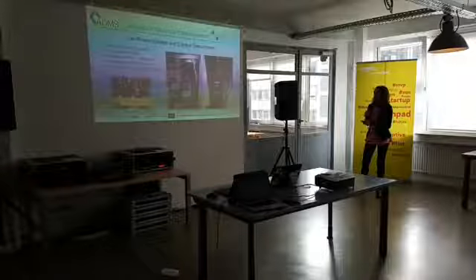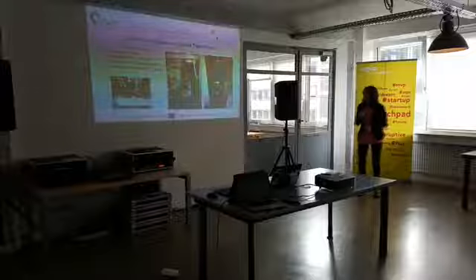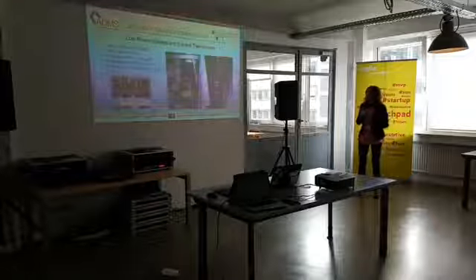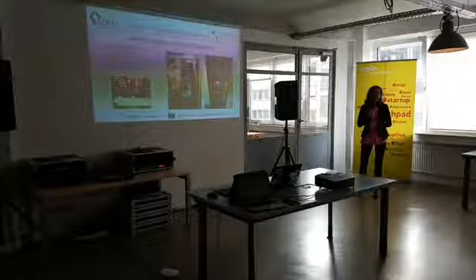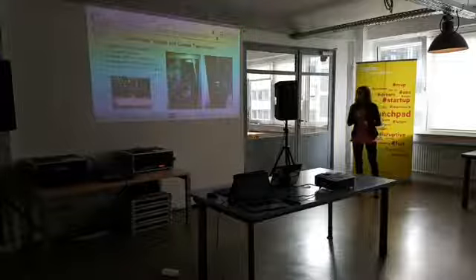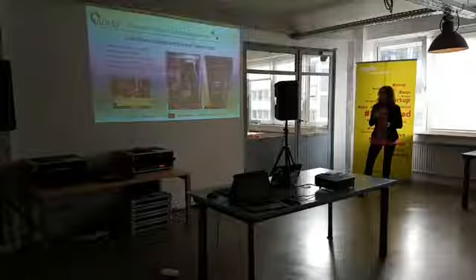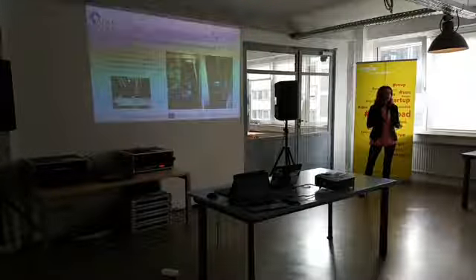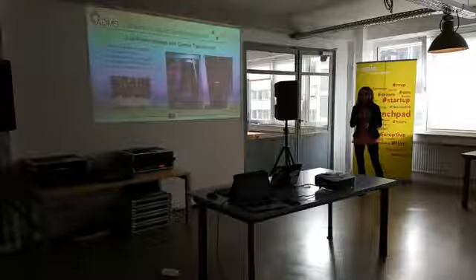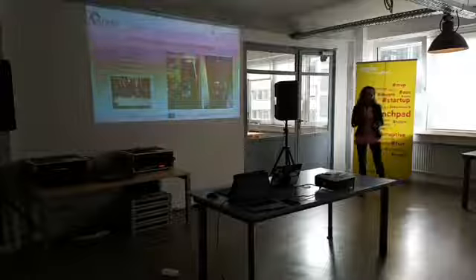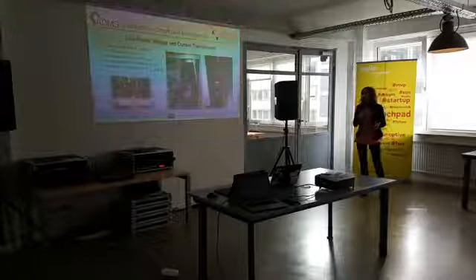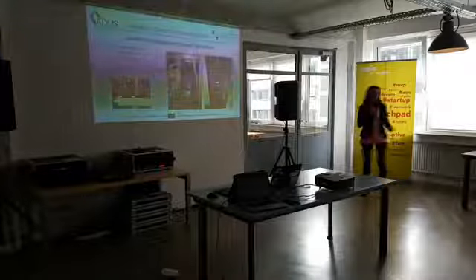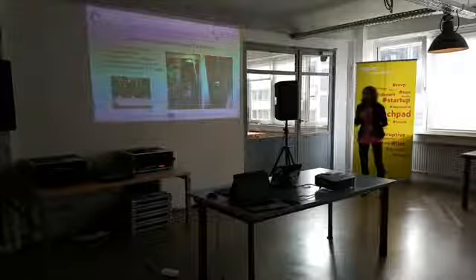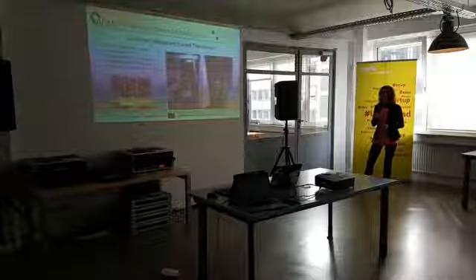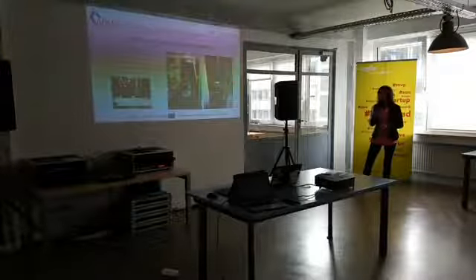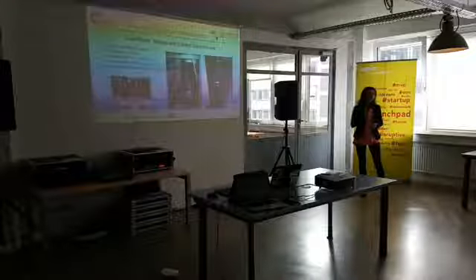Here, there are some examples of installation in indoor substation, 24 kilovolt. I wanted to underline that all of the technical features that were shown before have to be also integrated in equipment that grants other requirements that each DSO can ask. For example, most of the DSOs want galvanic insulation due to safety reasons. And also they ask for low impact solution because they need to install the sensor in already existing architectures. Reliability is required to be very high, and sensors usually are also well seen to be multi-purpose.